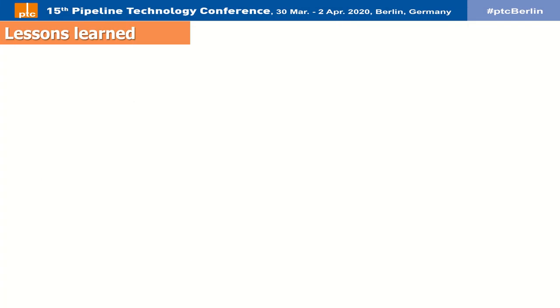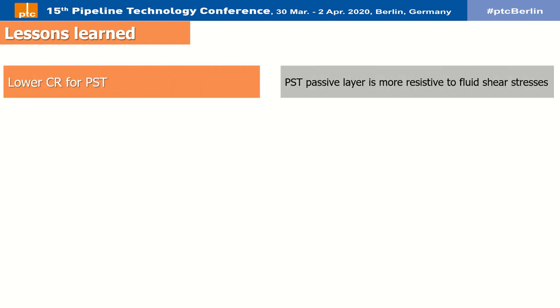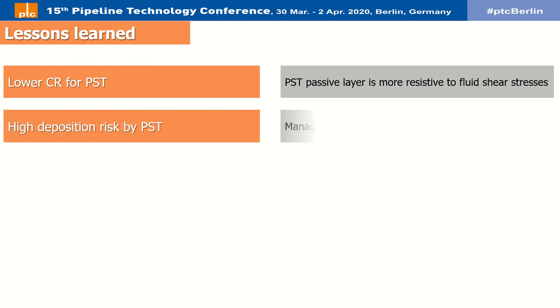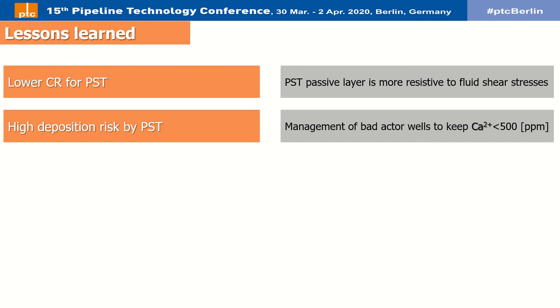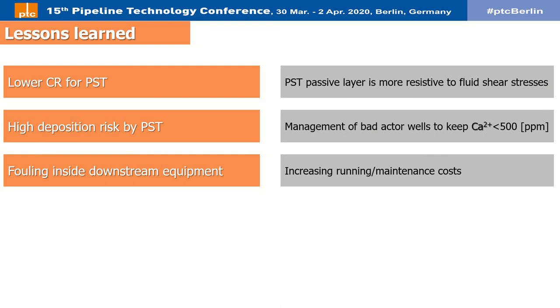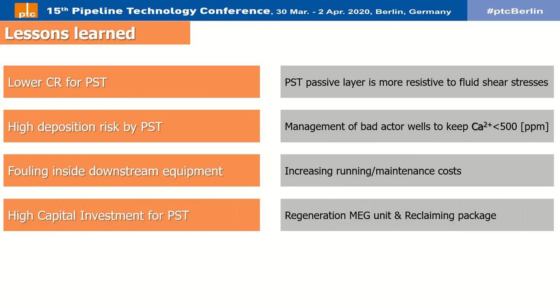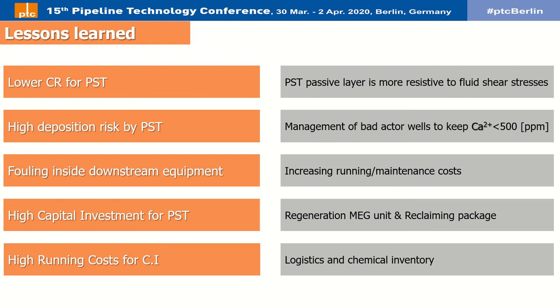Although pH stabilization and corrosion inhibitor methods each have their own pros and cons, successful implementation strongly depends on the operating conditions and system fluctuations. pH stabilization results in a lower corrosion rate and the passive layer is more resistive to fluid shear stresses, but it poses higher risks of deposition and requires management of bad actor wells. Both methods carry risks in downstream equipment that increase running or maintenance costs. pH stabilization requires high capital investment, whereas corrosion inhibitor injection incurs extra operational costs since it is not recycled in the system.